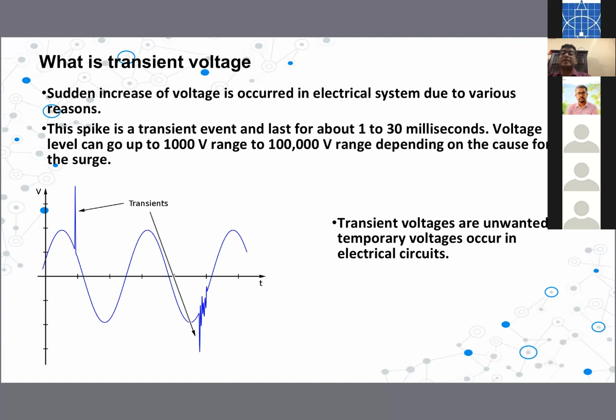So let's move on. Let's try to understand what transient voltage is. If you take an AC voltage waveform, it's a sinusoidal waveform. In the ideal case, this waveform is uniform, but due to certain reasons, there can be a sudden increase in the voltage waveform. But this sudden increase of voltage, or in other words voltage spikes, won't last for long. It will last only for a very short time, like 1 to 30 milliseconds. And the voltage amplitude in certain cases goes up to the 1000 volt range, and in certain cases it can go up to the 100,000 volt range, depending on the reason for the voltage spike or transient voltage.